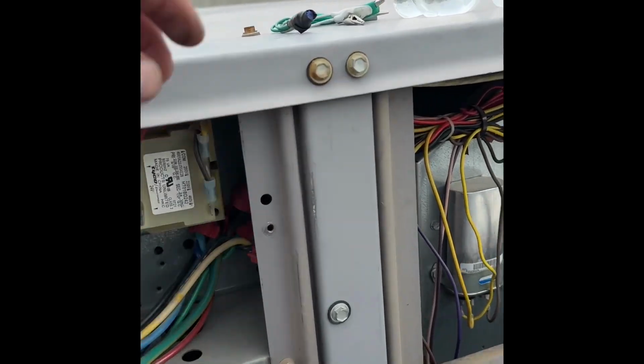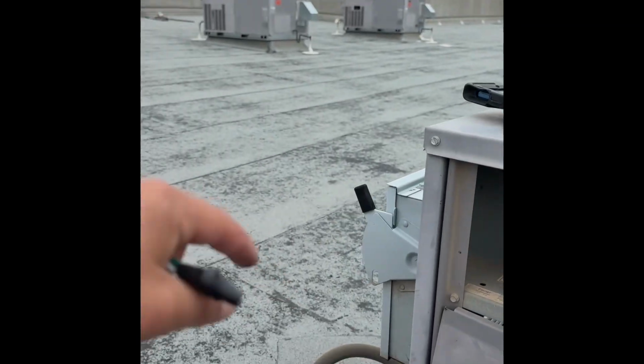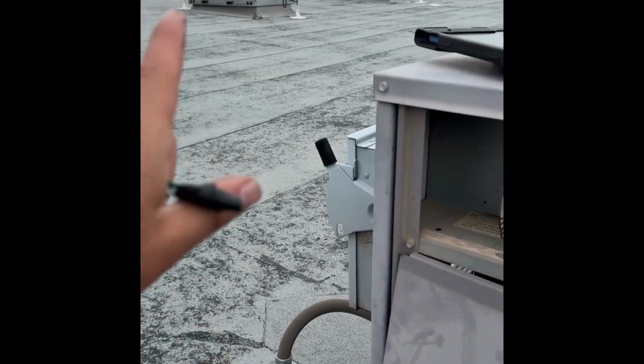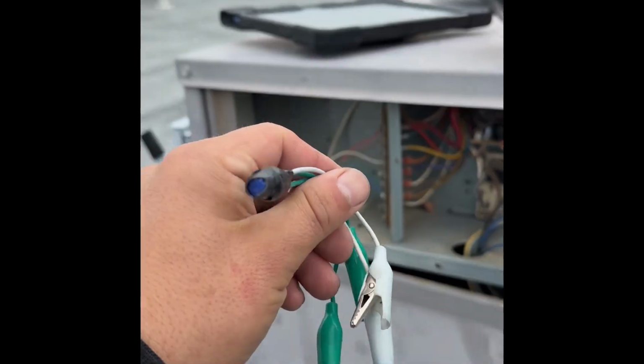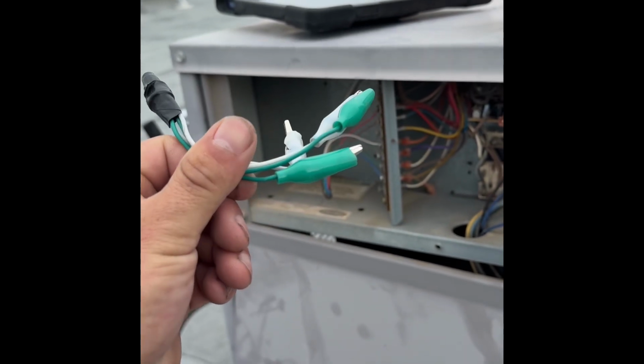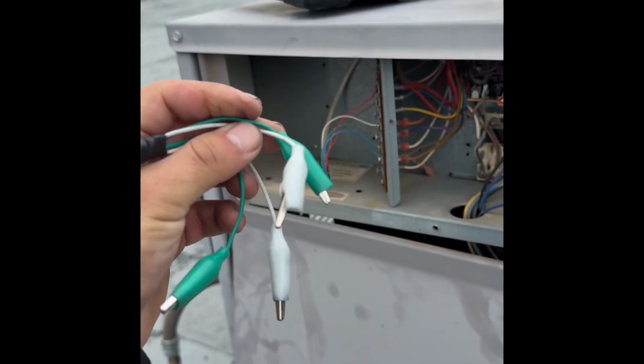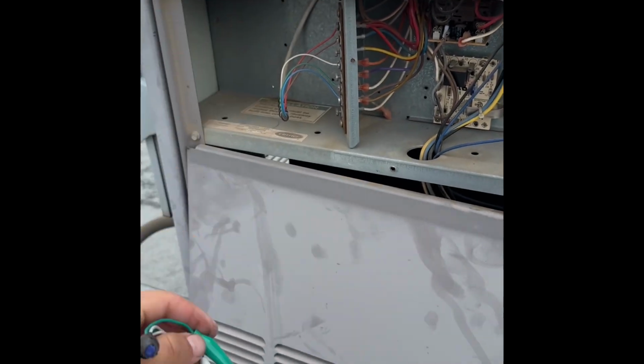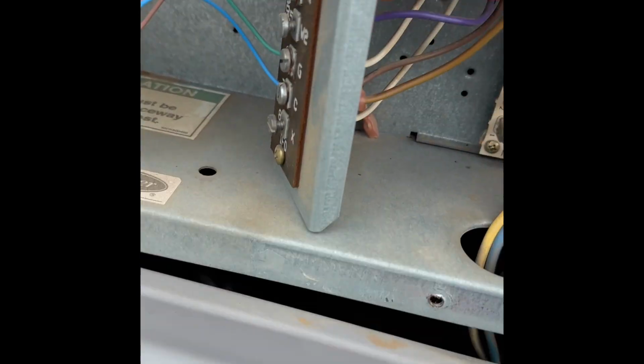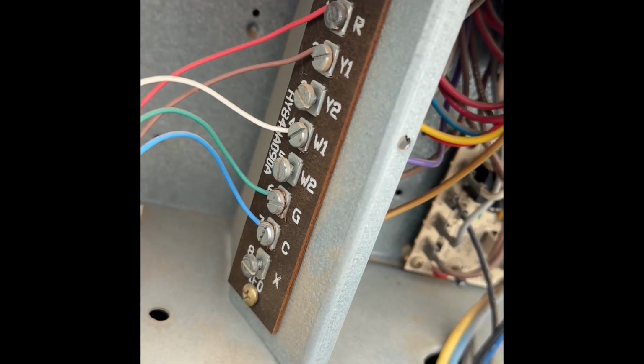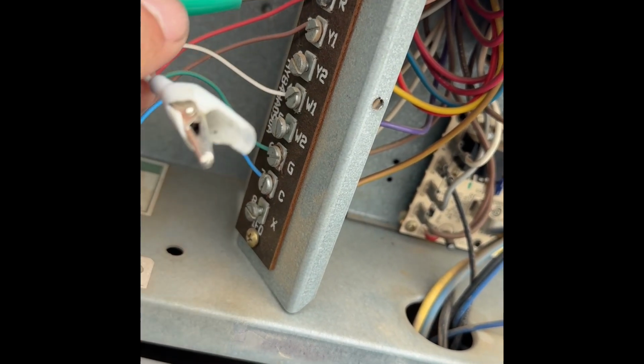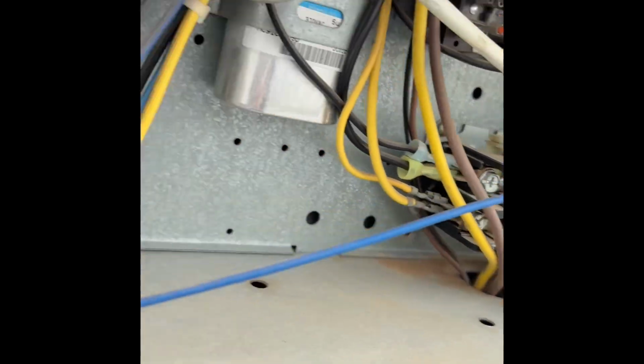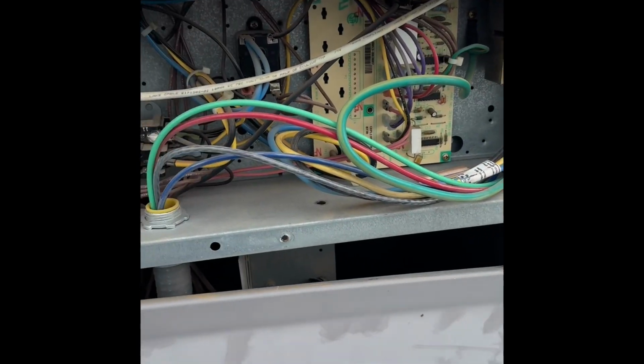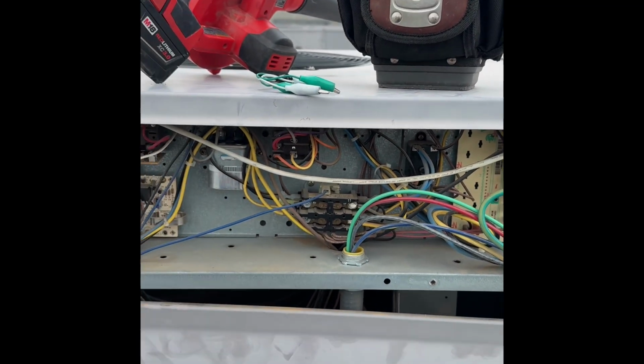And yeah, instead of going down to every thermostat inside the building and back up again to check the unit, make yourself a set of jumpers like these for the new guys. A lot of the OGs, a lot of the veterans, you guys already have these made, probably a bunch of them. I got like 6. I know that much. And instead of going to the thermostat, you're gonna put your jumper clips on R, on Y1 for cooling, the compressor contactor, which is right there, and 1 on G for the fan to energize in cooling. So we're gonna go ahead and skip over to that part right now.